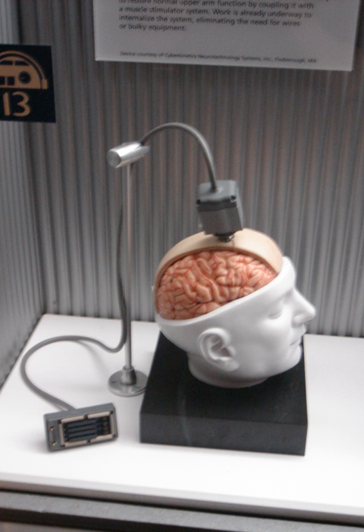One hurdle to overcome is the long-term implantation of electrodes. If the electrodes are moved by physical shock or the brain moves in relation to electrode position, the electrodes could be recording different nerves. Adjustment to electrodes is necessary to maintain an optimal signal. Individually adjusting multi-electrode arrays is a very tedious and time-consuming process. Development of automatically adjusting electrodes would mitigate this problem. Anderson's group is currently collaborating with Yu Chong-Tai's lab and the Burdick lab to make such a system that uses electrolysis-based actuators to independently adjust electrodes in a chronically implanted array. Image-guided surgery is used to precisely position brain implants.